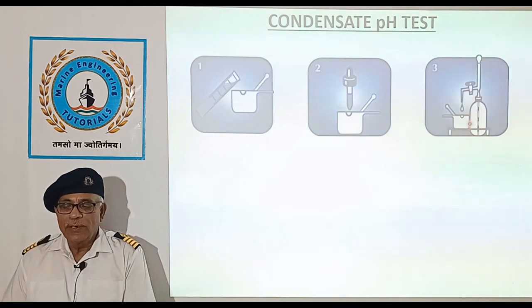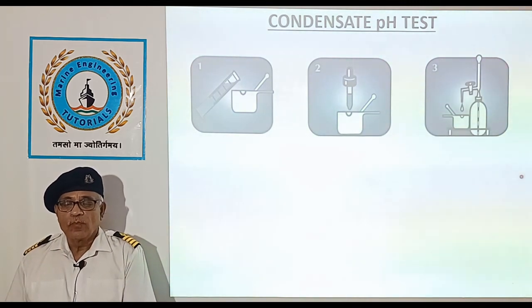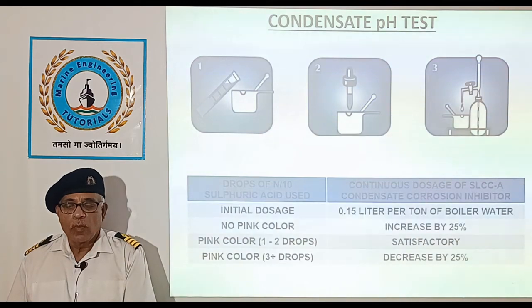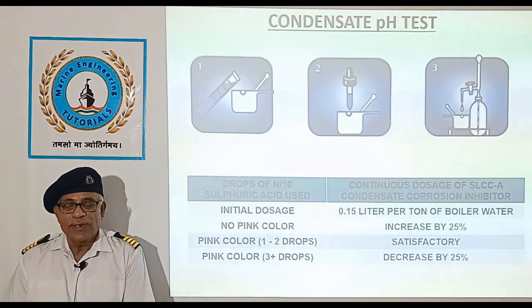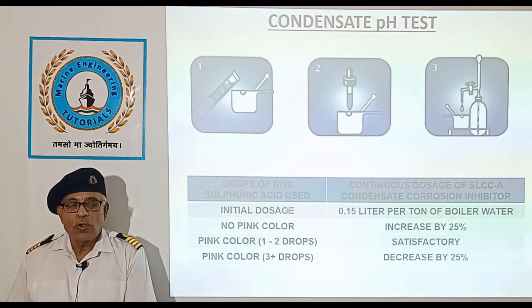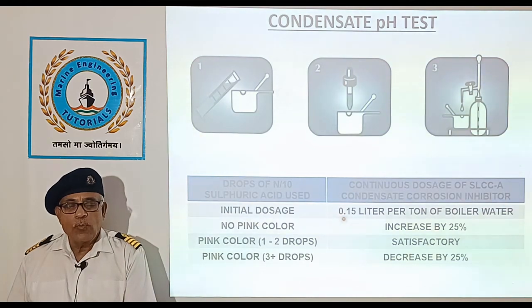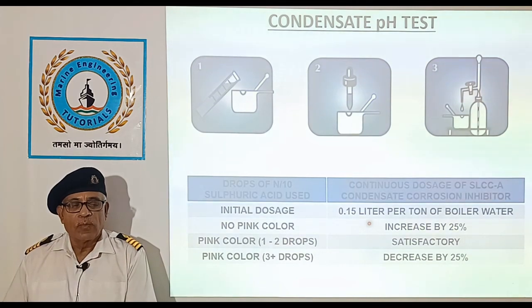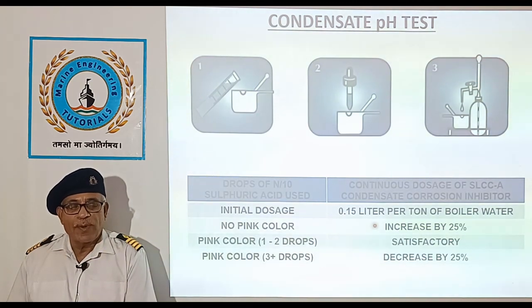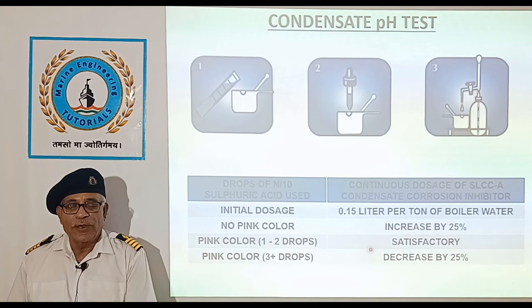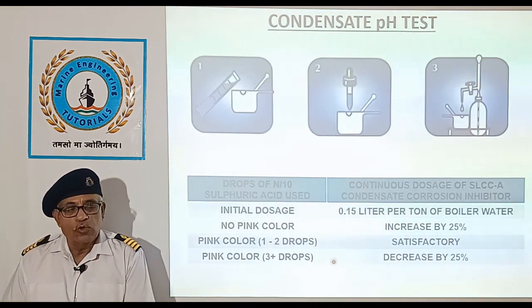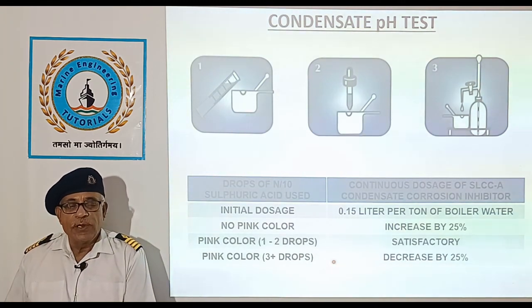Add sulfuric acid N/10 drop by drop until the pink color disappears. Record the result and adjust dosage as necessary. Initial dosage of condensate corrosion inhibitor is 0.15 litre per ton of feed water. If there is no pink color, we need to increase the dosage by 25%. If we are able to neutralize with 1 or 2 drops, it is a satisfactory range. In case 3 or more drops are used to neutralize, we need to reduce the dosage by 25%.